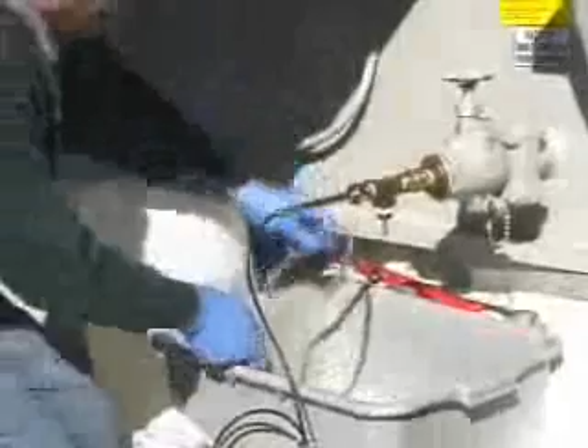So in that case, we took off the quick connector. We're draining any moisture from the manifold, and we're going to place it back in its box. You can see that there's oil still draining from the connection on the drain valve. In this case, now we're going to remove the adapter that we placed on it, but there's going to be quite a bit of oil behind it, so we have to make sure that it's captured properly and not spilled onto the ground.